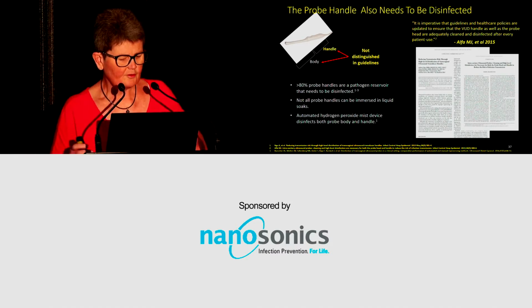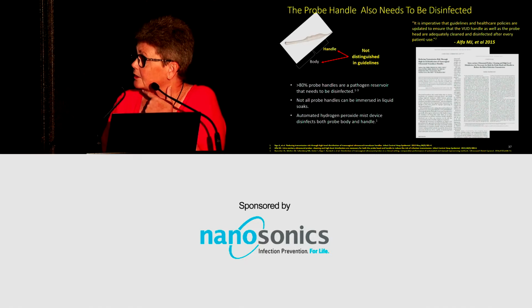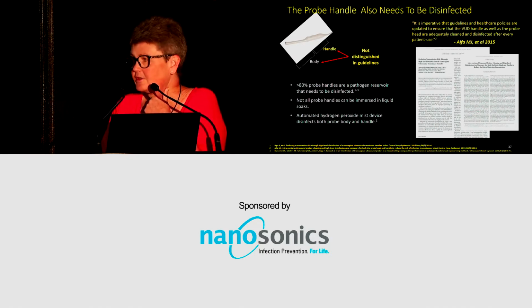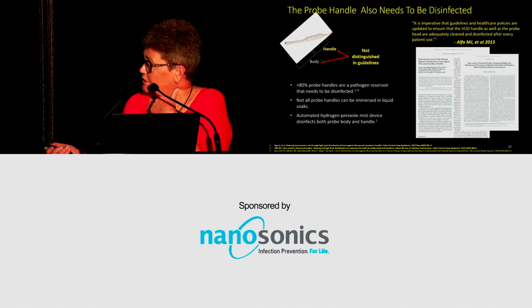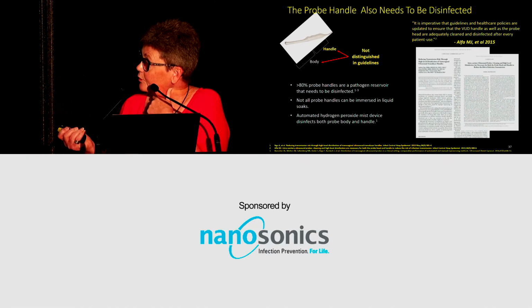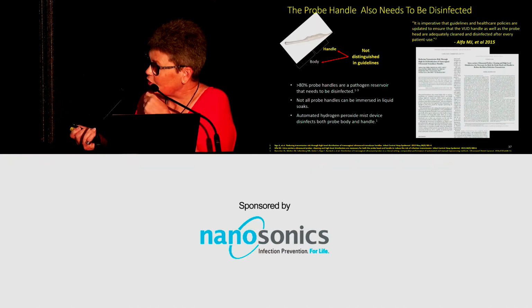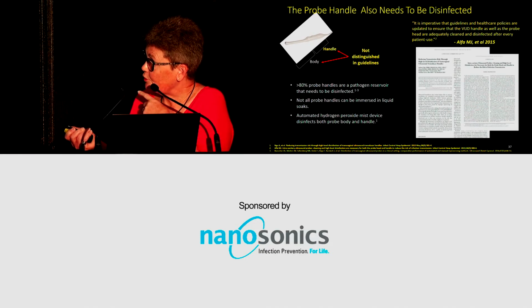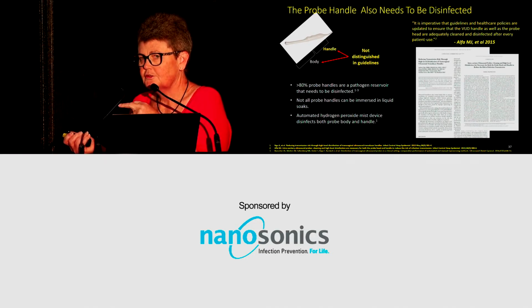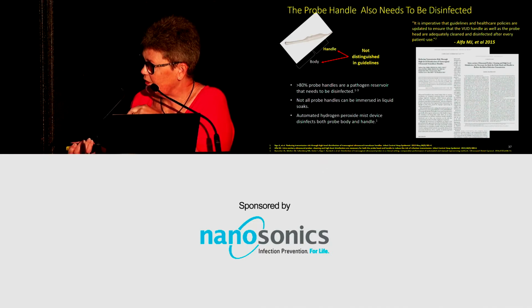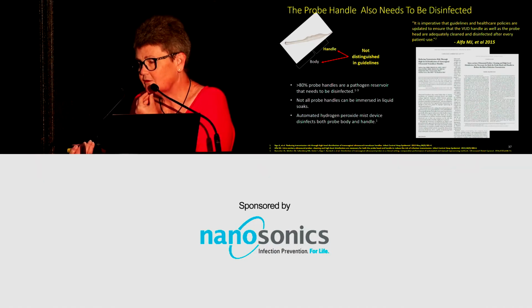Another point that I need to raise with you is that the probe handle can also become contaminated, and it too needs to be disinfected. And there have been papers showing problems when this has not occurred. Michelle Alpha, I mentioned her before, says it's imperative that guidelines and policies are now updated to ensure that vaginal ultrasound devices have their handle as well as the probe head adequately cleaned and disinfected after every patient use. So here, concerns around transmission of HPV. Other papers have been published showing us that more than 80% of probe handles are a reservoir for infection. Not all probe handles can be immersed in liquid soaks, and automated hydrogen peroxide mist devices disinfect both probe bodies and handles.